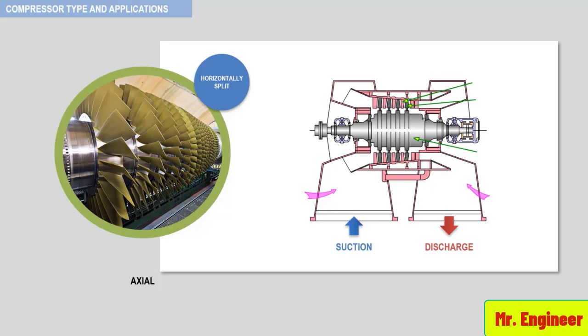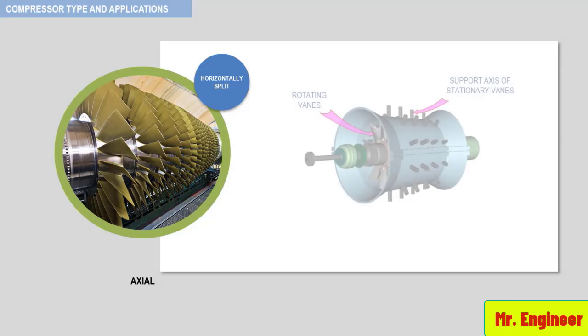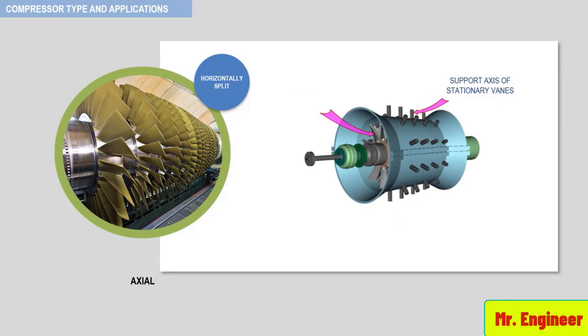As seen in the schematic, the rotating element consists of a single drum on which several rows of rotating vanes with aerofoil cross sections are attached. The vanes of successive rows keep decreasing in height. Between each of these rows of rotating vanes there is a row of stationary vanes.